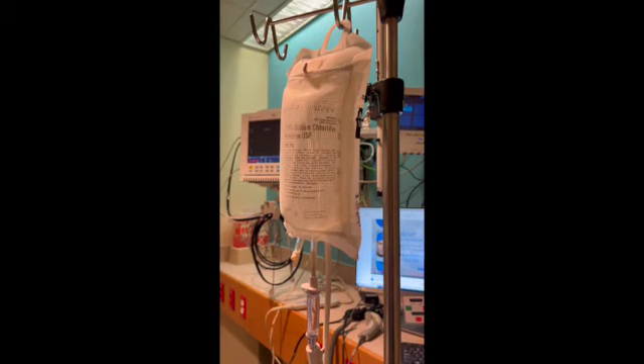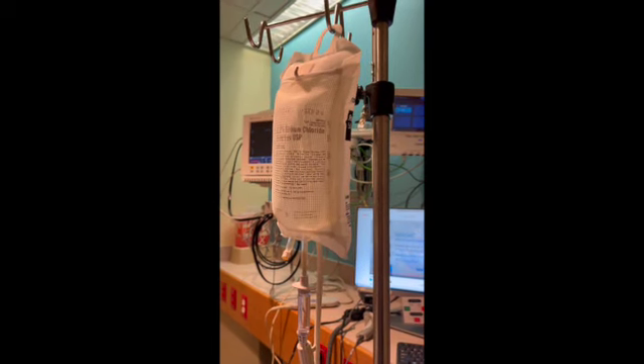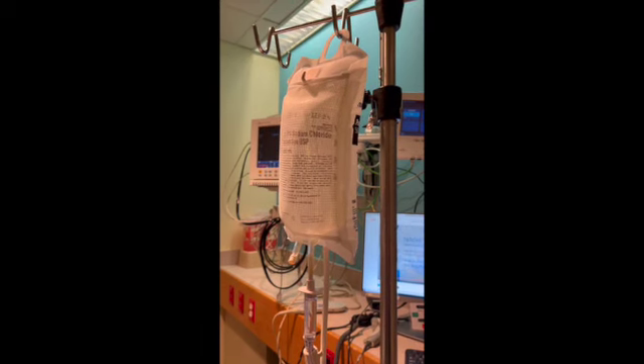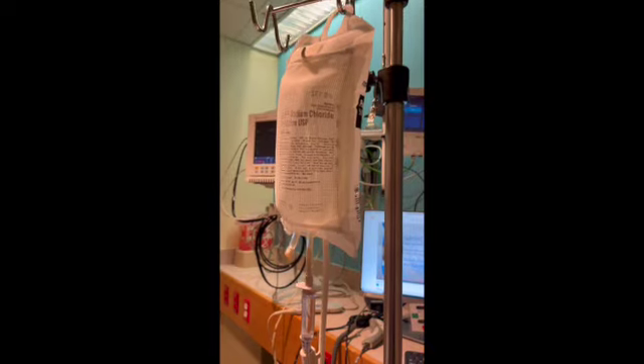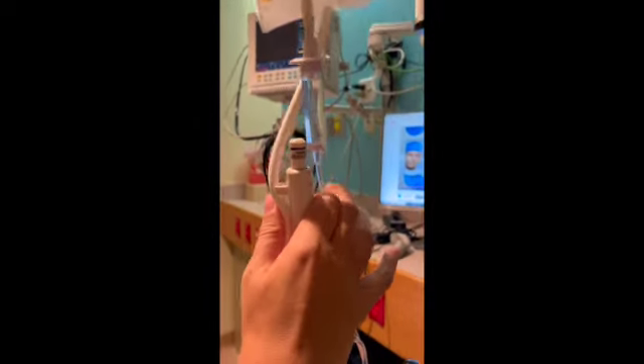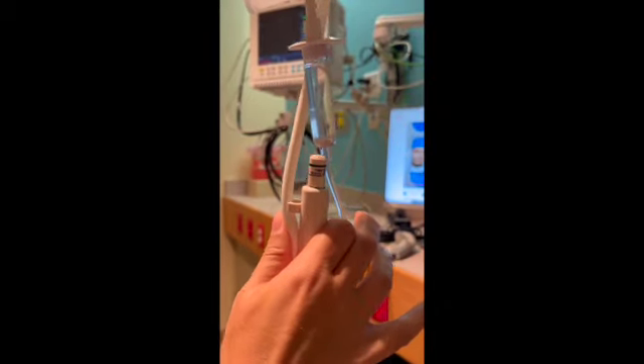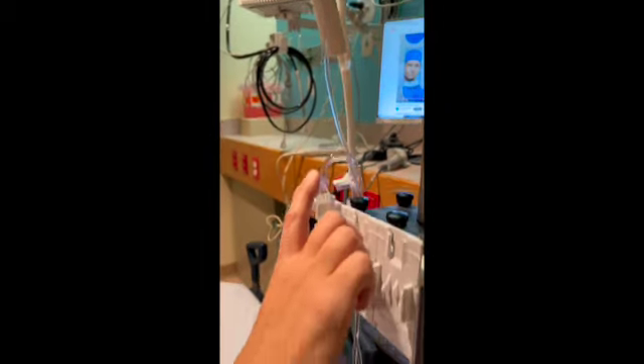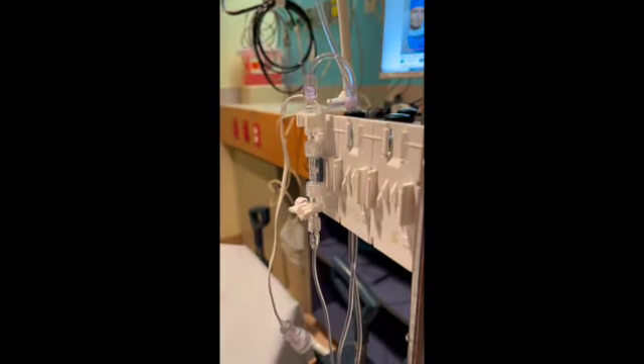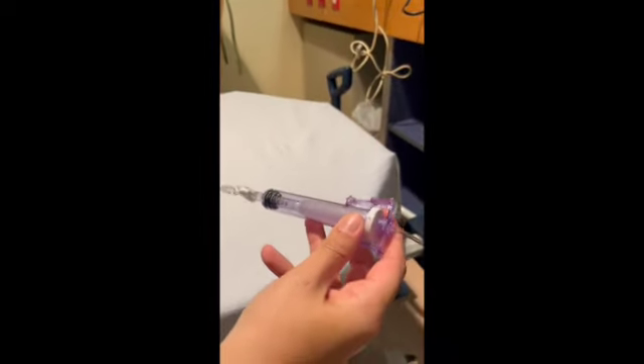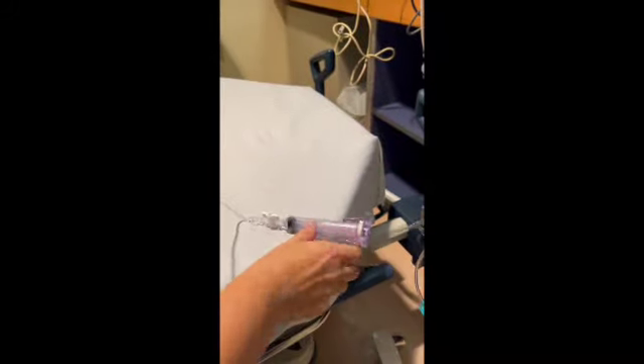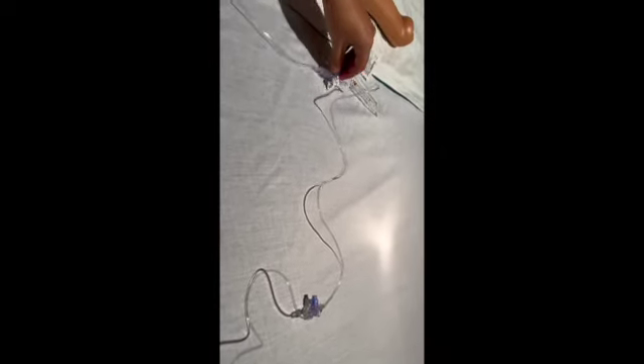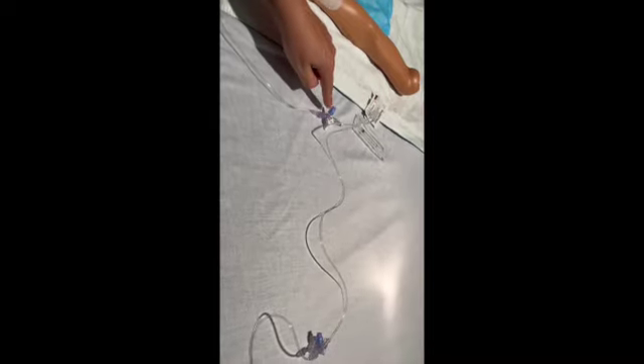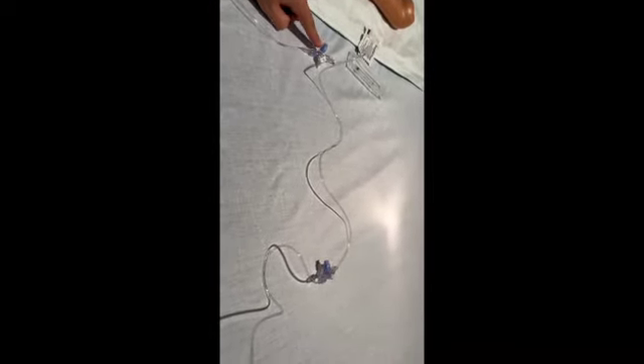Okay, so in terms of this new potential Safe Set system that we may or may not see in some of our patients, there are similarities and differences to the other system. The similarities start with the 500cc normal saline bag, the measurement manometer where you're going to pump up to the green marking, which is 250 millimeters of mercury, down to the transducer system, which is exactly the same. The differences start with the Safe Set waste syringe, which looks like a 10cc syringe, attached to the tubing, which attaches to the patient. Then there'll be two potential sampling ports, but we're going to always sample with the port closest to the patient, and each of the sampling ports will also have needleless ports to draw the blood from.